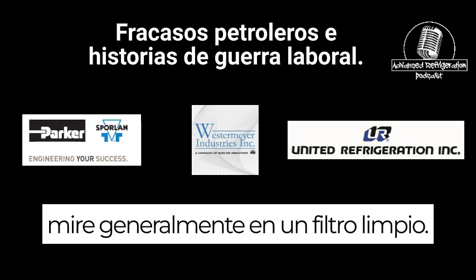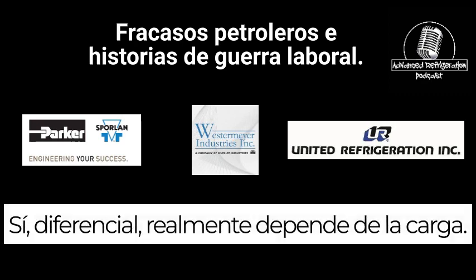Generally on a clean filter, Brett, what do you say? Yeah, that's a good assumption, 1 pound differential. I mean, it depends on the load, really.